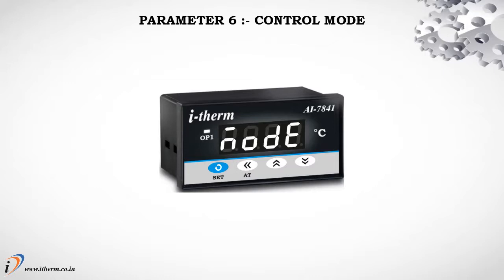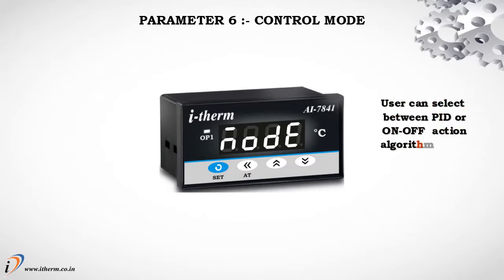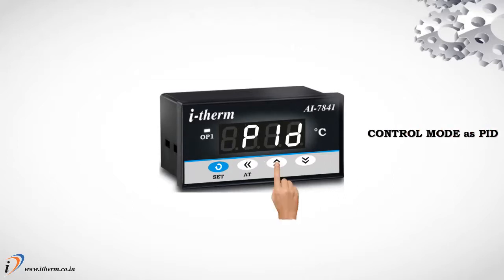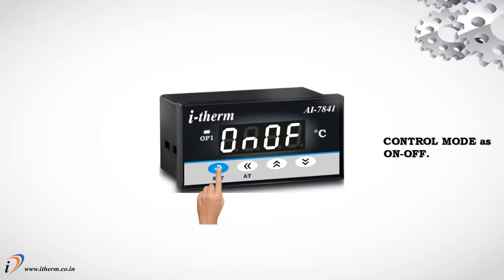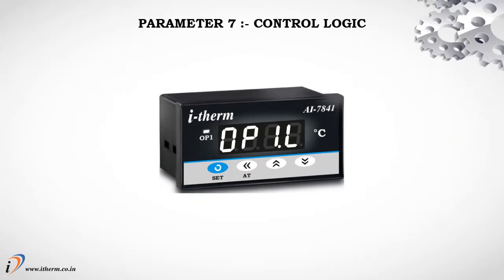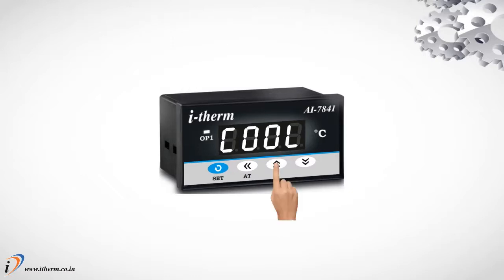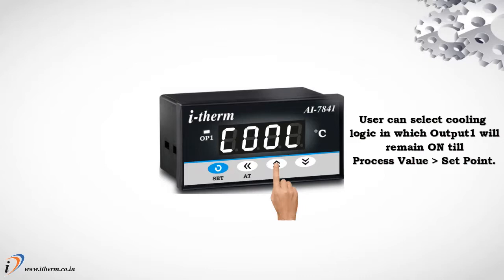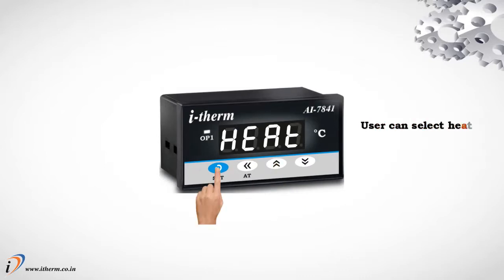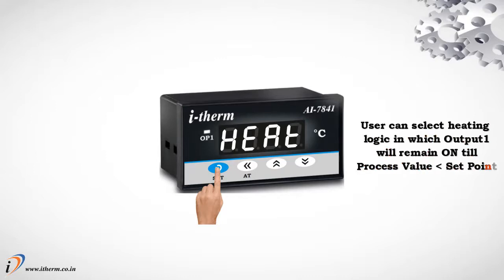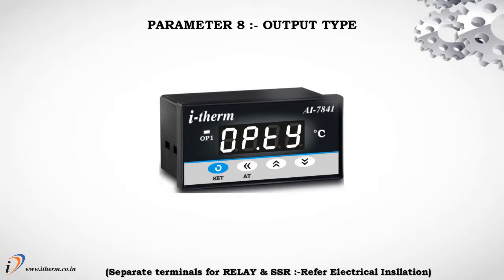Parameter 6, Control mode. User can select between PID or on-off action algorithm to be adopted for output. Control mode as PID. Control mode as on-off. Parameter 7, Control logic. User can select cooling logic in which output 1 will remain on till process value is more than set point. User can select heating logic in which output 1 will remain on till process value is less than set point. Parameter 8, Output type.